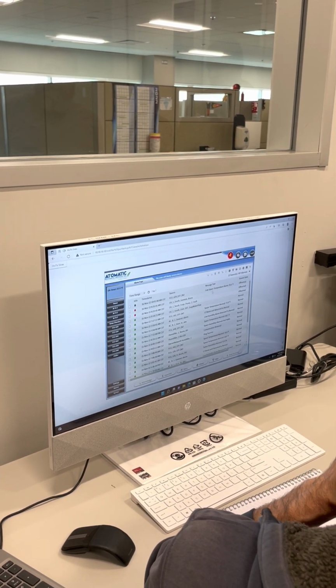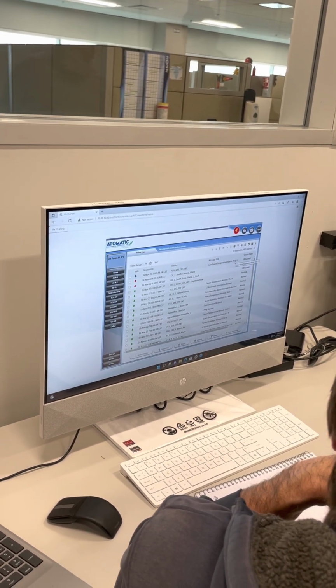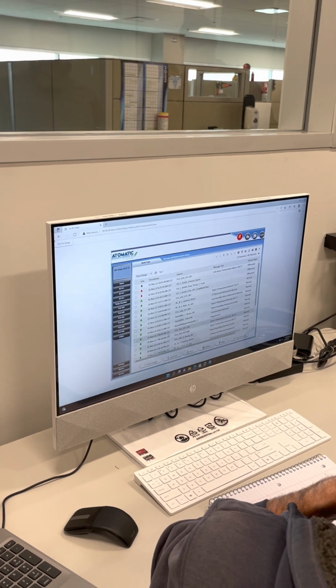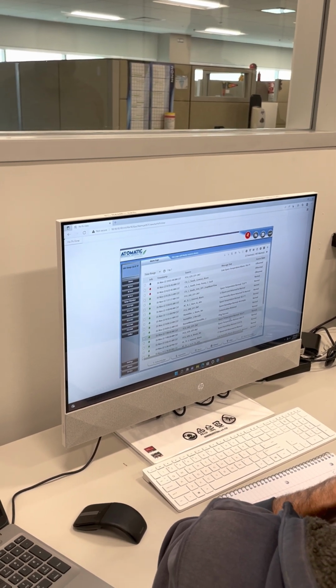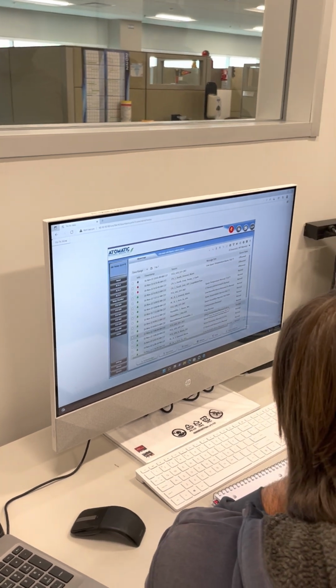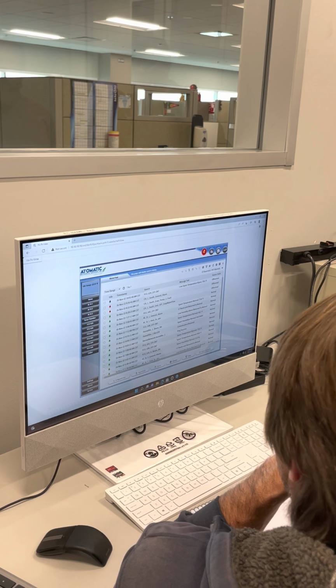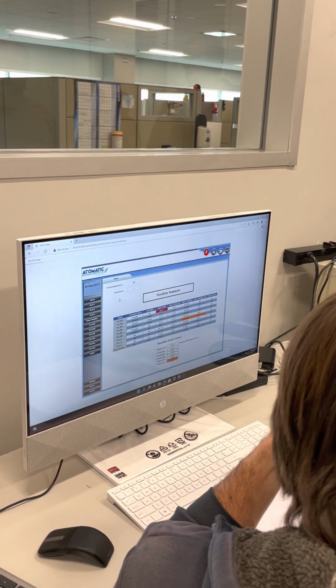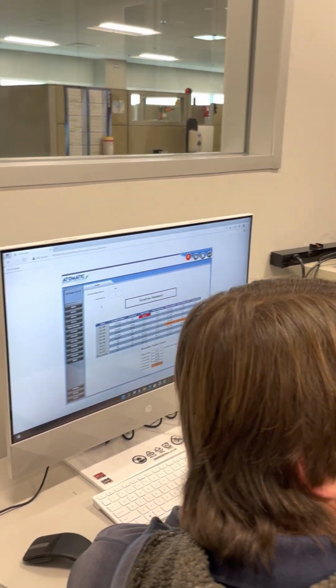You see how it showed low space temperature alarm, and then it shows you what the temp was. When it clears itself, you're going to get space temperature normal. So what does acknowledging do really? Well, it clears your home page for one. It's just like reading an email. It's acknowledging that hey, somebody came in here and somebody is aware that this did it for you.